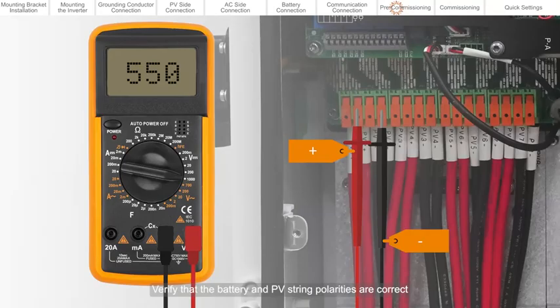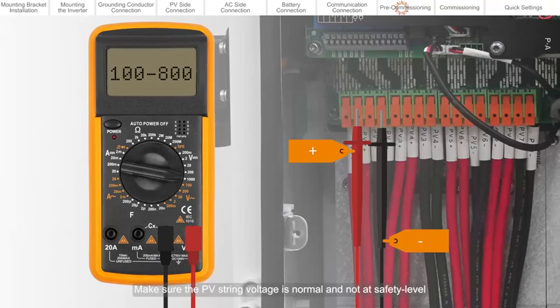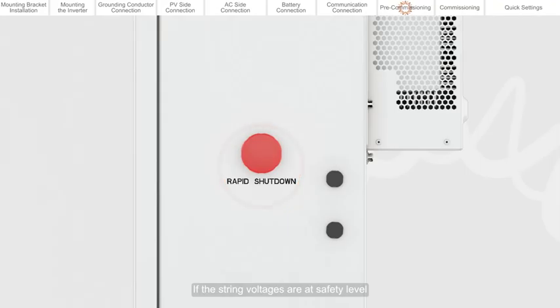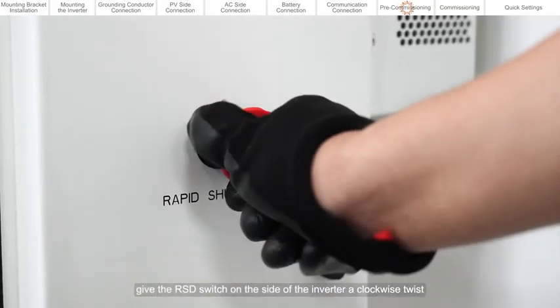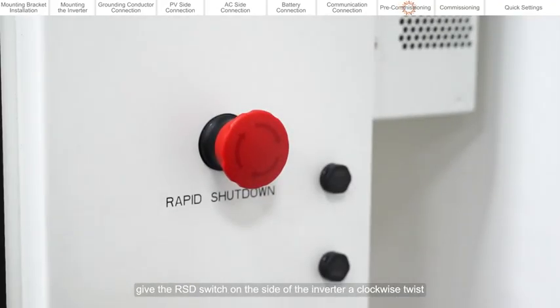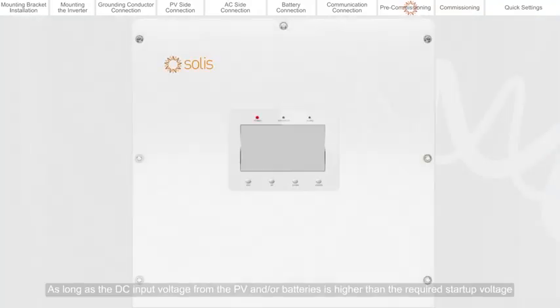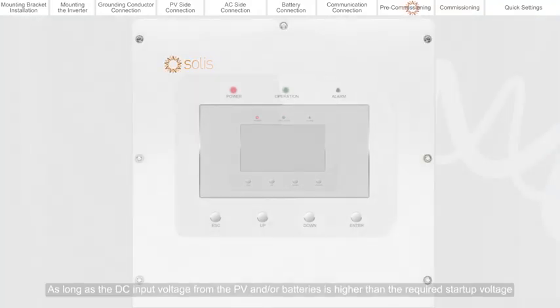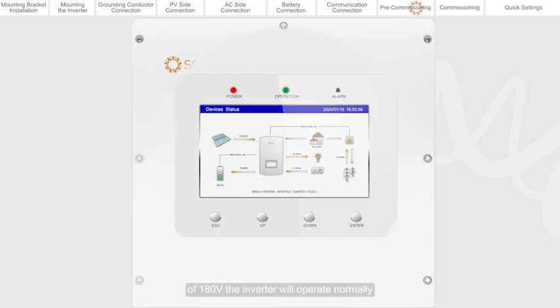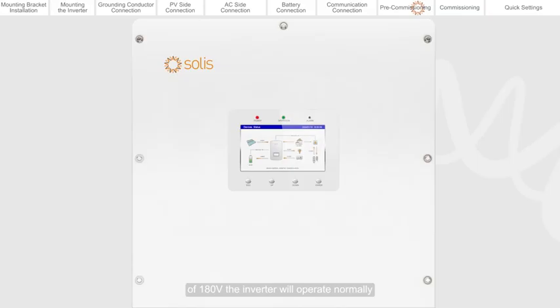Verify that the battery and PV string polarities are correct. Make sure the PV string voltage is normal and not at safety level. If the string voltages are at safety level, give the RSD switch on the side of the inverter a clockwise twist. As long as the DC input voltage from the PV and/or batteries is higher than the required startup voltage of 180 volts, the inverter will operate normally.